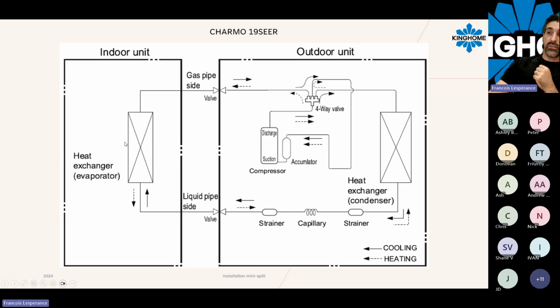Again, the evaporator will do its job. It will gain some heat. So the refrigerant will gain heat here. And then on the other side, it's supposed to have changed states to gas, low pressure gas refrigerant. We will have the suction line here to make sure our superheat will be completed. And then it goes back to the four-way valve going into the inner portion here.